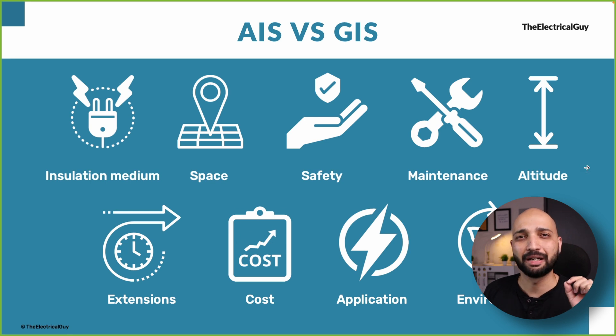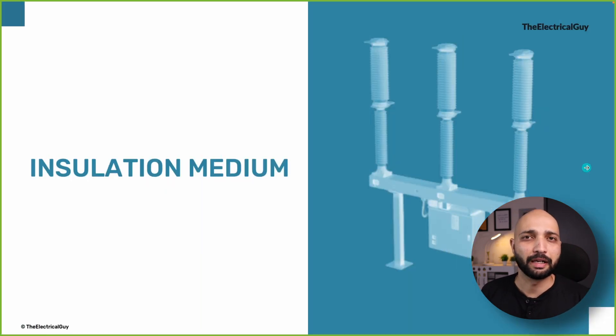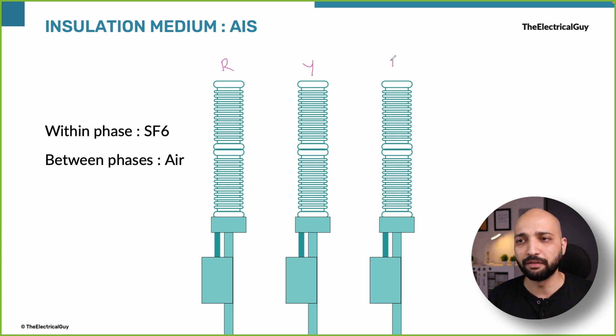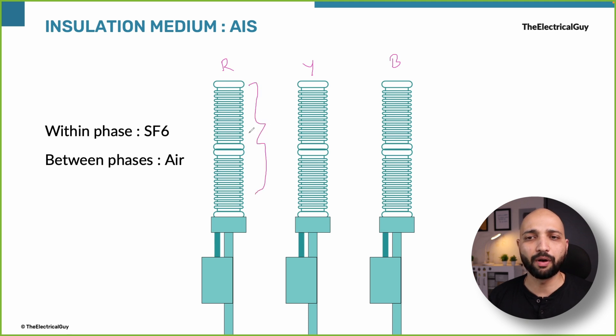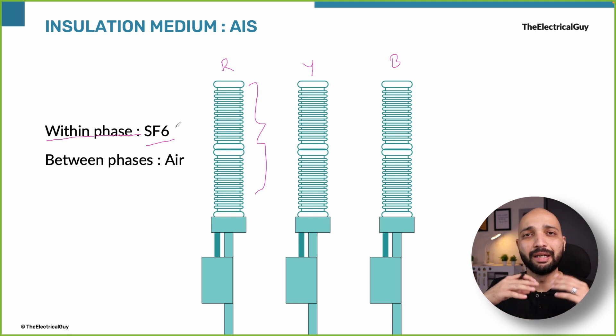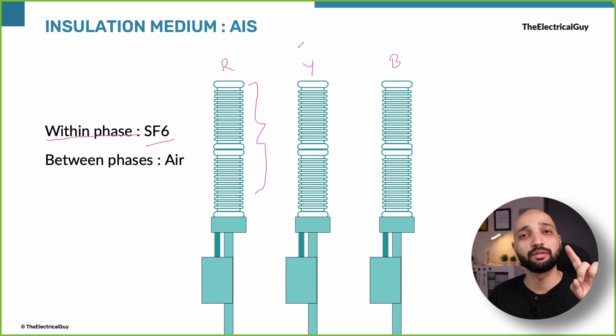Let us first start with the main difference, and that is the insulating medium. There are two concepts here: insulation within the phase, and insulation between the phases. So let's say this is our R phase of a circuit breaker — whatever insulation is provided inside this phase is what we call insulation within the phase. Generally it is provided by SF6 gas in high and extra high voltage switchgear, but it can also be vacuum or any other gas with insulating properties.